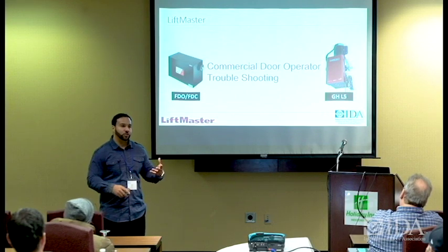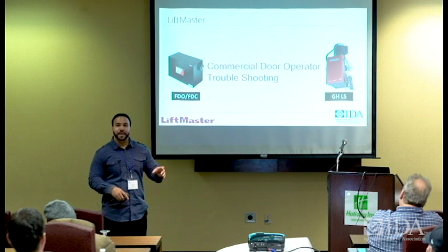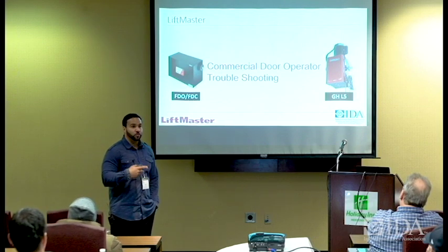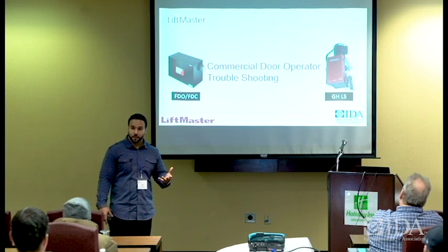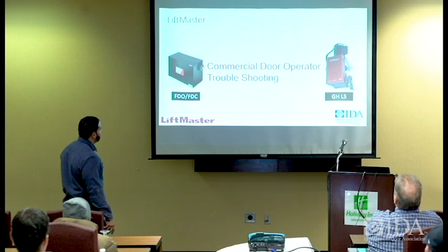You gotta make sure that the electrician is properly engaged and understands that you gotta have the right gauge, the right wire run. Everything has to work in conjunction, because these do have an amp load. And when they're under load, the amps increase. And everybody in the room knows that when your voltage drops, your amps spike, you're looking for some trouble, okay? All right, so with that being said, we're gonna jump into this.